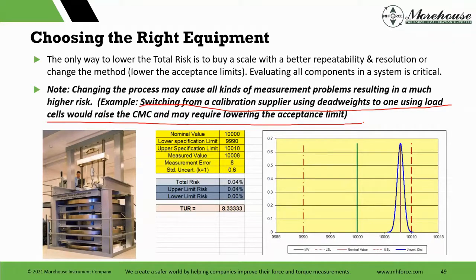I don't know, but you need to evaluate it using that formula that I showed and say, will it make sense? What happens? Are they going to fail more instrumentation? Are they following the right guidelines? Are they taking the uncertainty into account, or are they just reporting it? There are so many labs out there that just say, hey, I take the uncertainty into account by not considering it. Simple acceptance happens all the time. I just want simple acceptance. That pushes the risk back to you. Just understand it. If we're all on the same page, we're okay. If we're not, you're going to absorb the risk. And when I see labs absorbing the risk, a lot of them don't know they're absorbing the risk.